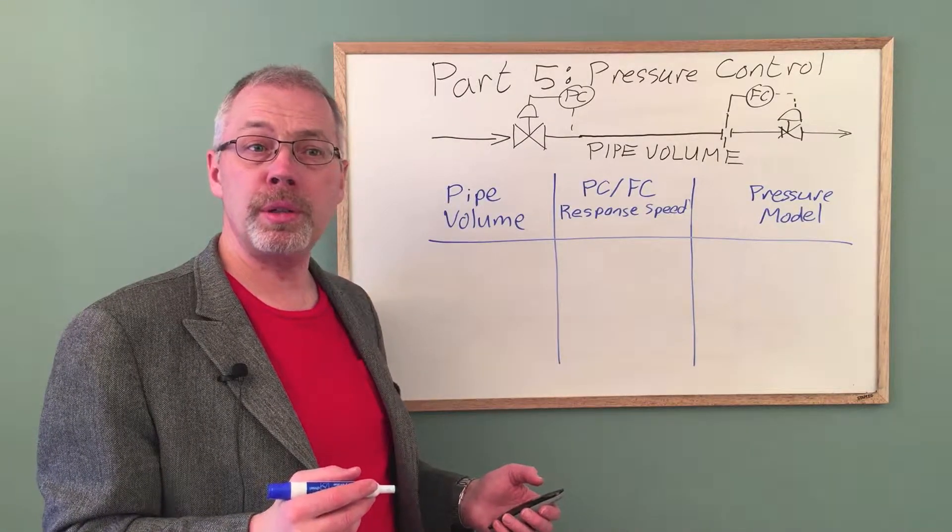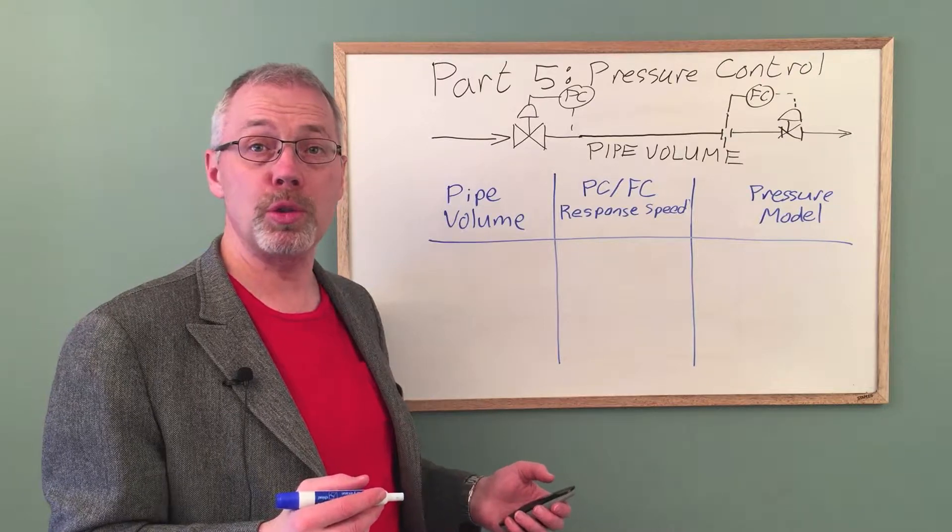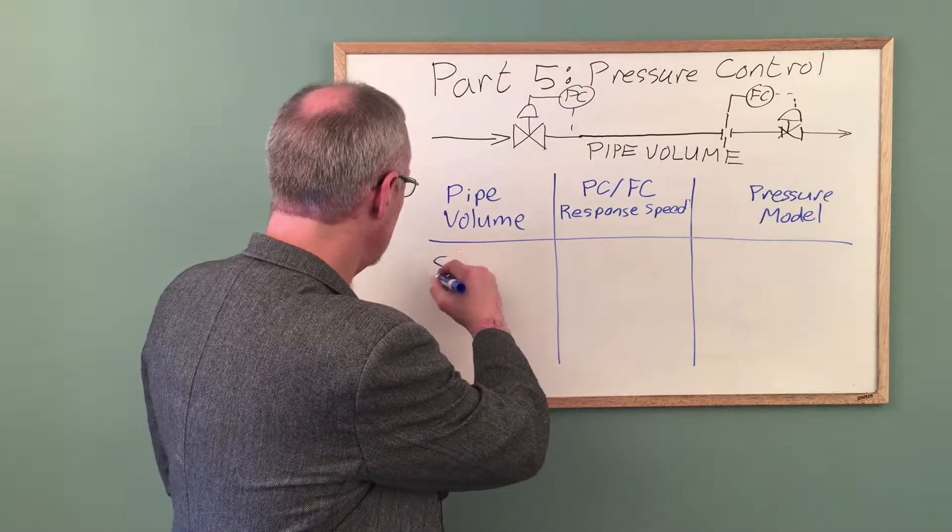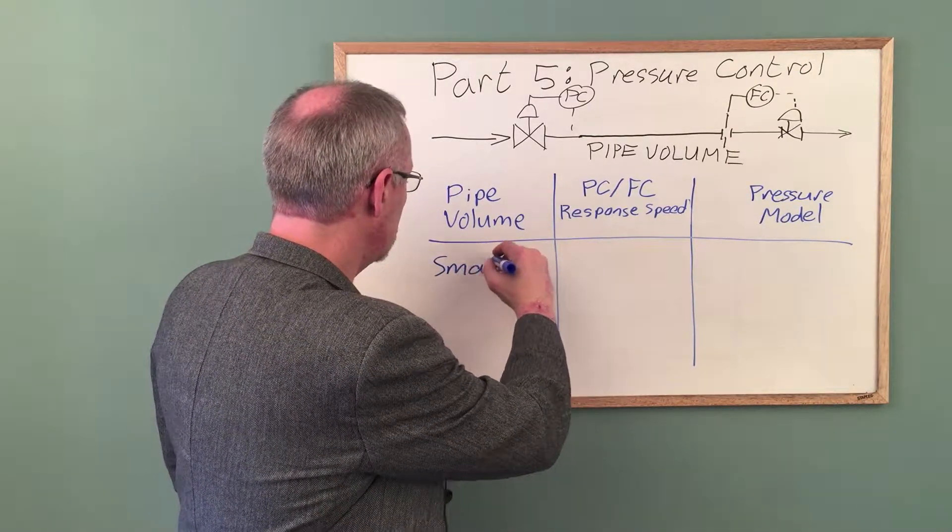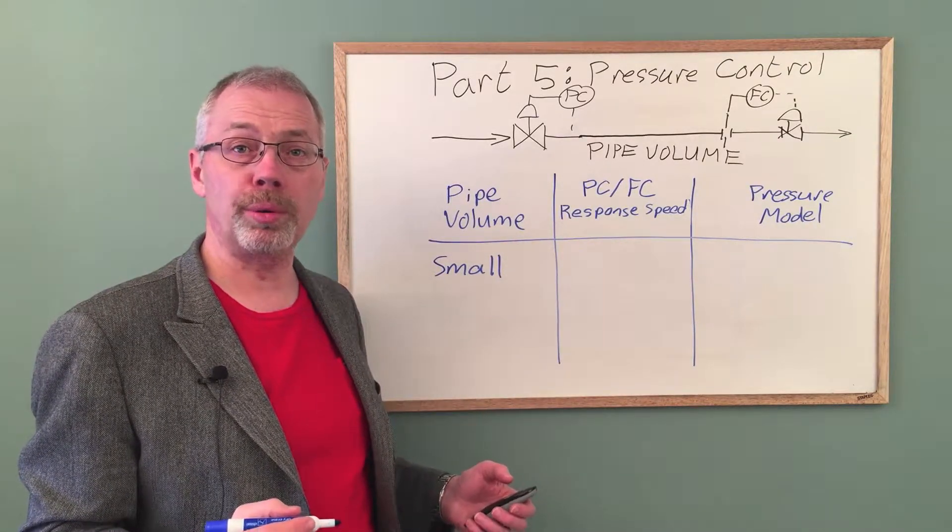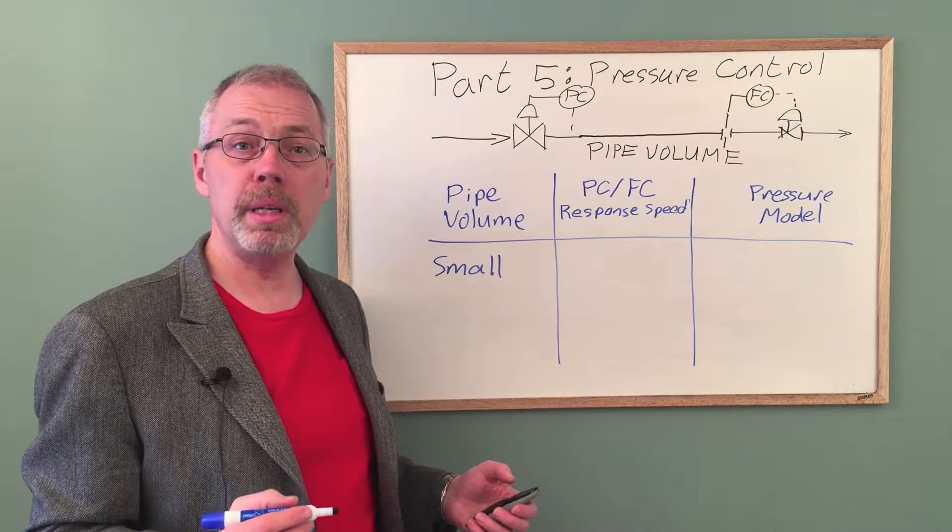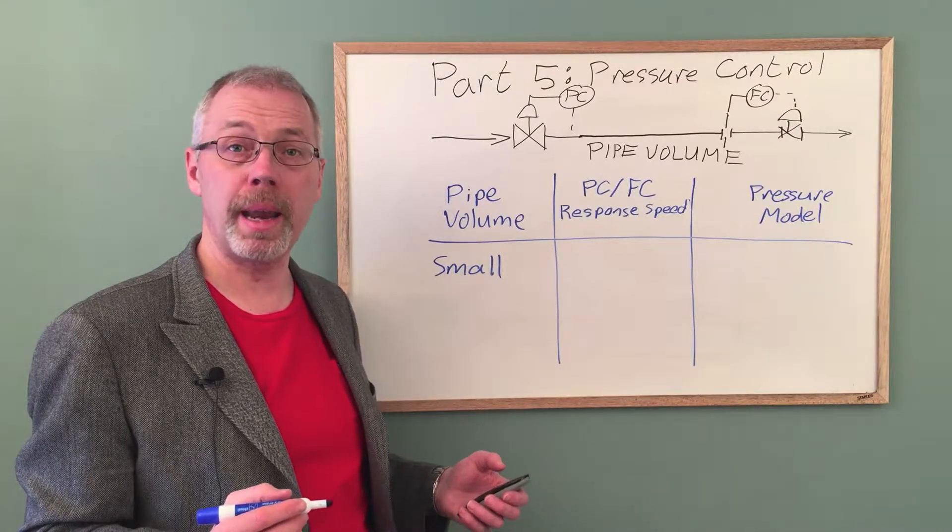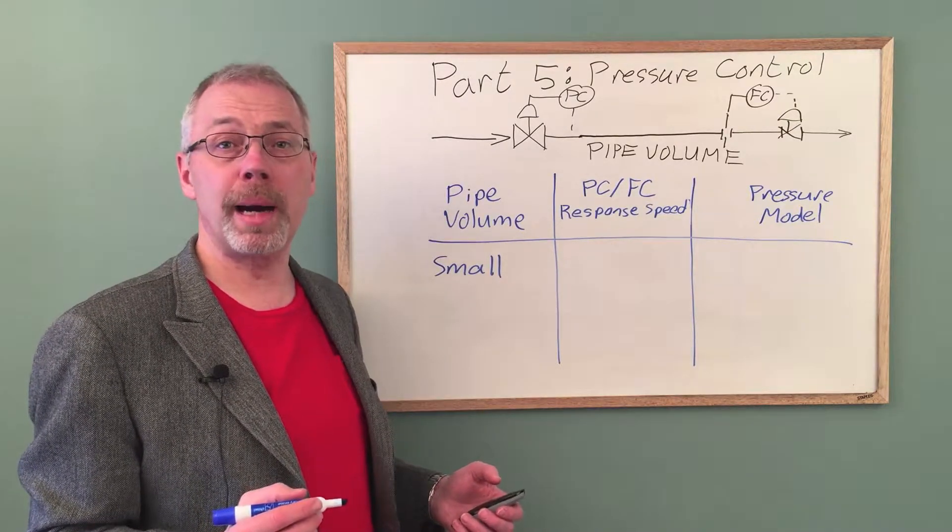First, let's consider the case where the pipe volume is quite small. In this case, a change in the pressure control or flow control output has an immediate impact on both the pressure and the flow rate. This is an interacting system.